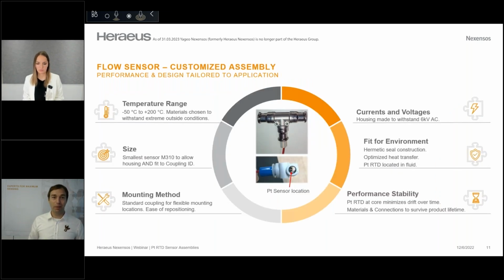Now, this is the summary slide, or the result of that whole exercise. So what's the performance of that combined puzzle now of that sensor? You see on the top left temperature, so you can put it into the Antarctica, you can put it into the Sahara, you can drive the equipment at the extremes with the processes and the materials that we have chosen. So -50 to +200 degrees. In extreme conditions, it will work. We used very small elements to make sure that we can protect the sensor, but it would also fit into that coupling. Mounting method, I explained that you can very flexibly position and reposition that sensor among the entire cooling system of the charging equipment.